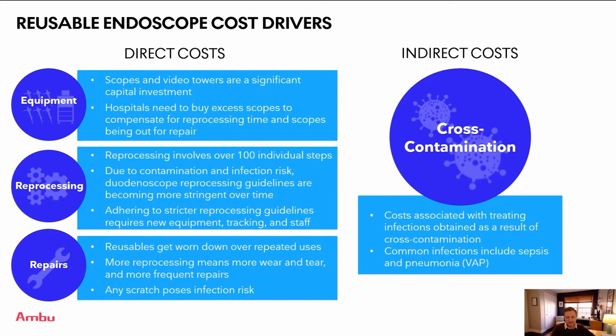On the reprocessing side, there are over 100 individual steps involved in reprocessing a duodenoscope. And what we've seen over time is that due to contamination and infection risk, the reprocessing guidelines are becoming more stringent, and that's leading to more cost as the reprocessing cycles become more difficult to achieve and to carry out successfully. And we saw that in the FDA study I mentioned before, even with additional training and with additional resources, steps are often missed because the reprocessing is just so complex, and that complexity means higher costs.